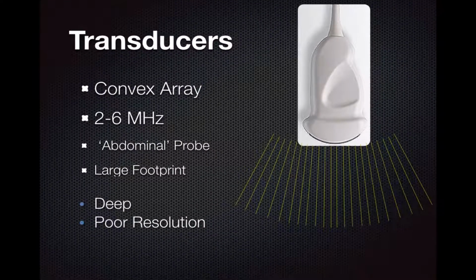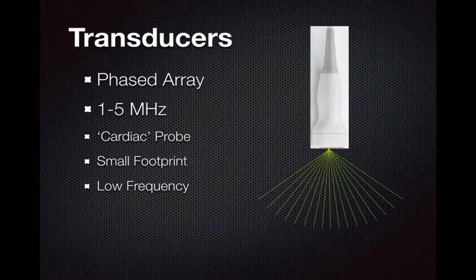So here's some of the main transducers we use. One is the curvilinear convex array probe, and this is a low frequency probe, so 2 to 6 megahertz, and it's often referred to as the abdominal probe because, again, it's low frequency, good penetration, but pretty poor resolution. It gives you a nice sort of global view, nice big footprint of the patient's tissue.